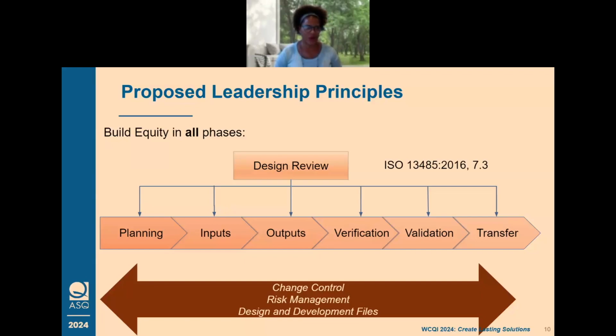I'll give a quick overview of the design control process based on the CFRs, which have recently adopted ISO 13485. You've got the planning process, which sets the stage for the entire development of the product, and then you create product requirements, user needs, and design inputs that get translated into specifications and outputs. Once you have all your output specifications and requirements, you create design builds, manufacture them, and then they get tested and verified to confirm they meet the design inputs. If the builds pass, you use them to perform validation.